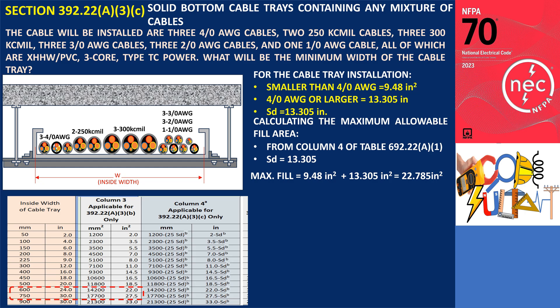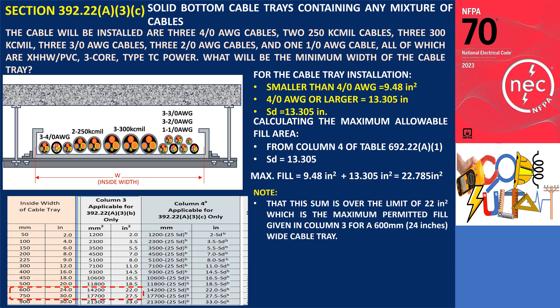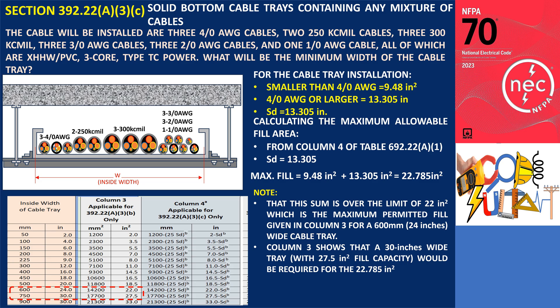Note that this sum is over the limit of 22 square inches, which is the maximum permitted fill given in Column 3 for a 24-inch wide cable tray. Column 3 shows that a 30-inch wide tray, with 27.5 square inches fill capacity, would be required for the 22.785 square inches determined from the calculation of Column 4, Table 392.22(A)(1). Therefore, to accommodate this fill, a 30-inch wide cable tray should be used.